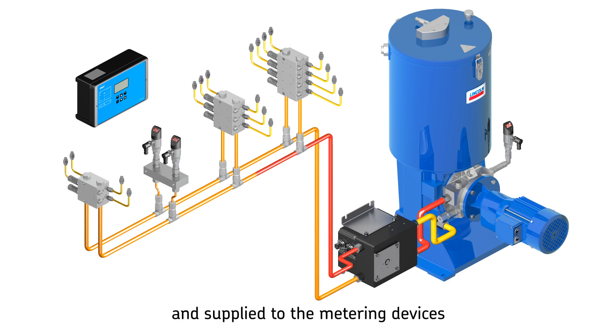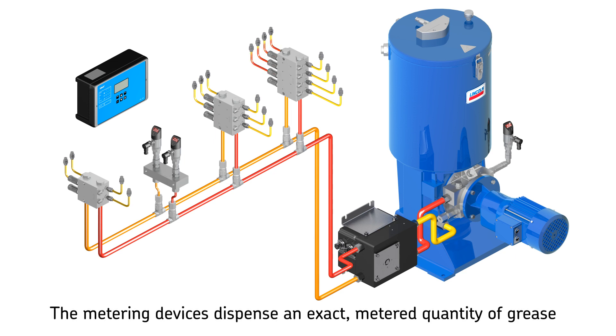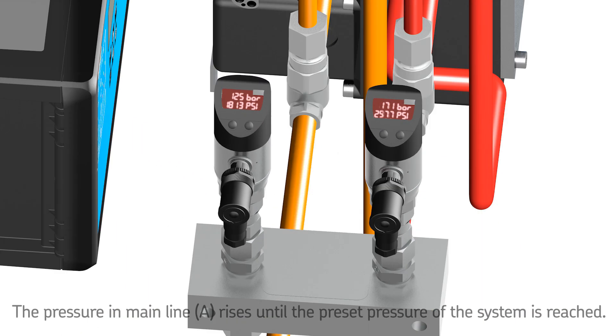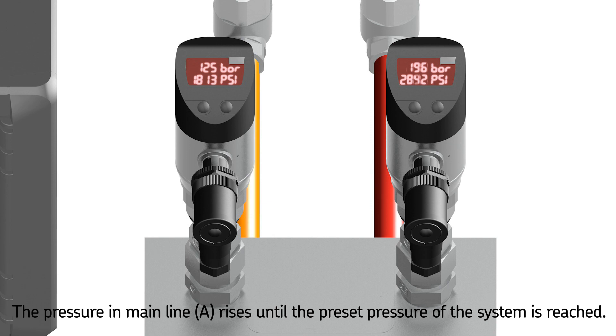The lubricant, conducted by the changeover valve, is supplied to the metering devices. The metering device pistons move into their adjusted end positions, dispensing an exact metered quantity of grease. Once all metering devices have dispensed their lubricant, the system is hydraulically closed, causing pressure in main line A to rise.